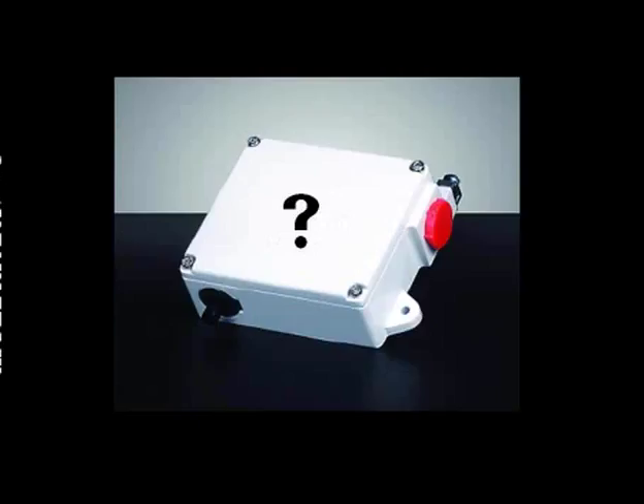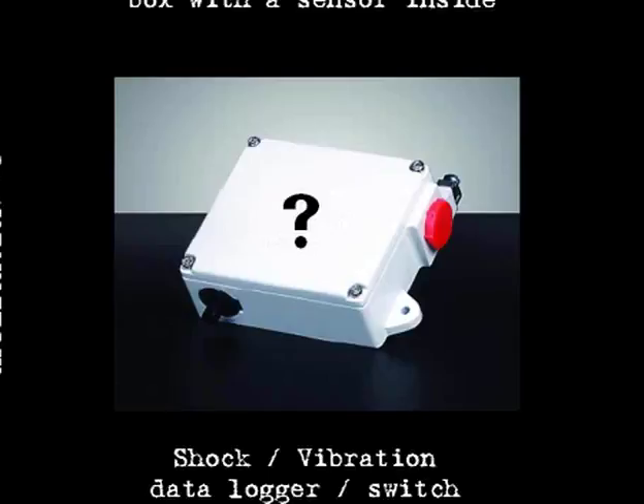So moving on, I think this is probably the last example we have today, where again the customer needs a shaker table, and this is the object they want to shake. The question mark there is because typically this is a box with a sensor inside, and sometimes that box would be a vibration or shock data logger. It could be a vibration switch, and the customer wants to, again, it's kind of a calibration application, but they don't really want to calibrate. They basically want to make sure that the box is doing what it's supposed to do. If it's a vibration switch that has to trigger at a 5G level, the customer wants to put 5Gs on that box and see if it triggers.